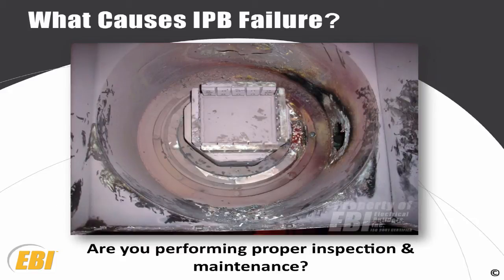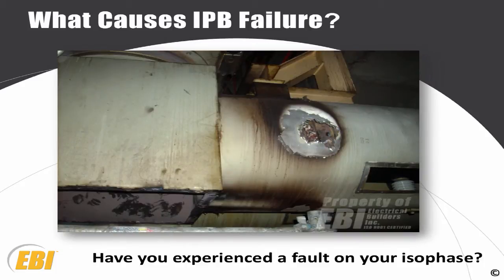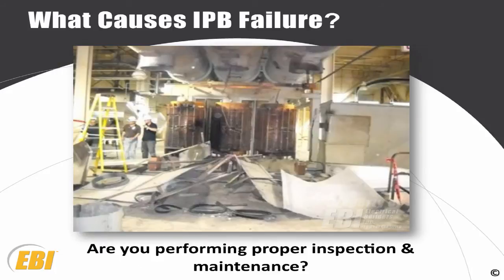This is actually looking into a seal-off bushing at a lead compartment at the generator. They could actually get inside and clean this seal-off bushing off, but the backside of the seal-off bushing was not accessible. So this is what happened. You notice the inspection cover that you can get into the insulator past where the failure was at. That gives you an access point to that insulator, but it does not give you access back to the seal-off bushing back next to the line compartment. This is what happens when one of those insulators come apart, when two of them come apart on the same phase. You notice the shock wave that went through the entire room.